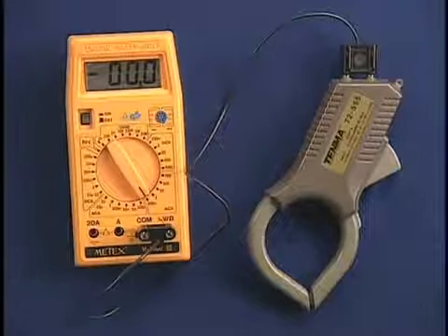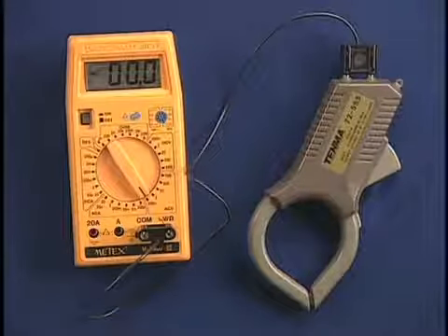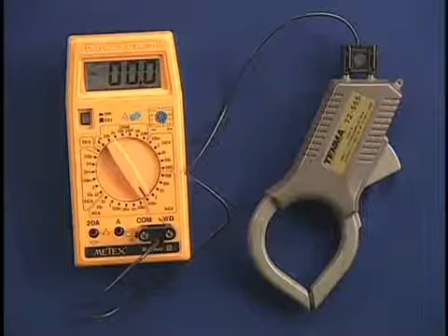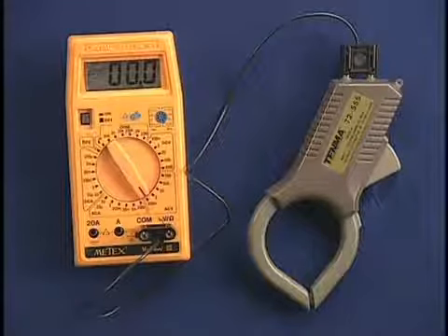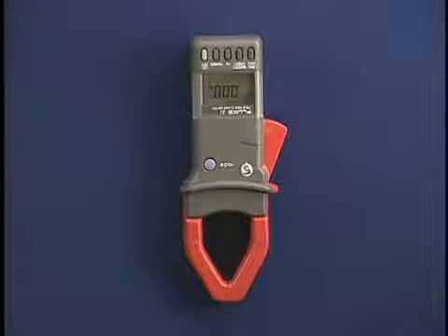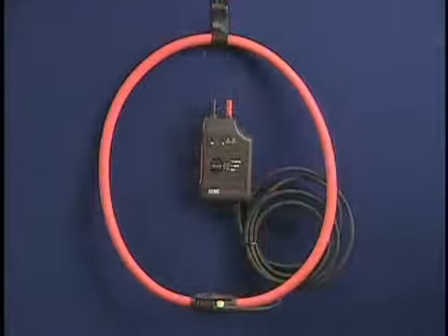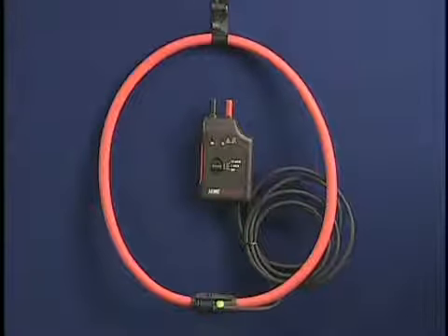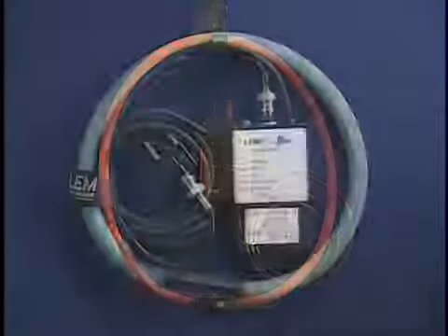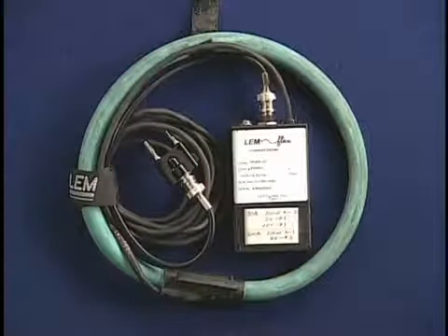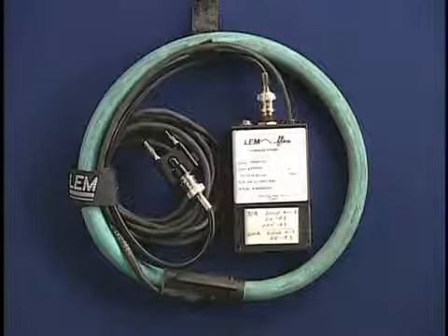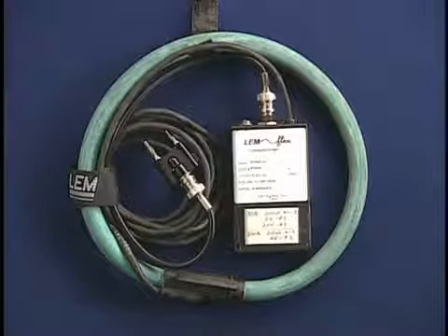It plugs into a digital multimeter with an AC millivolt setting. 1 millivolt equals 1 amp. This one, made by Fluke, has a min-max and averaging function, which is useful if you're measuring a fluctuating current. For large service conductor cables, bus ducts, and large water pipes, there's nothing like a 2-foot or 3-foot flexible probe. The unit plugs into a digital multimeter. Here are 2 such units.